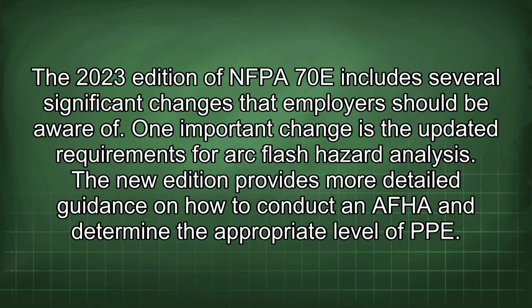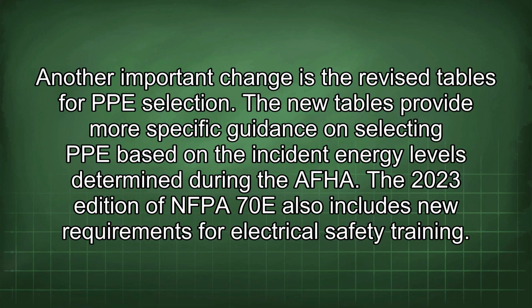One important change is the updated requirements for arc flash hazard analysis. The new edition provides more detailed guidance on how to conduct an arc flash risk assessment and determine the appropriate level of PPE. Another important change is the revised tables for PPE selection. The new tables provide more specific guidance on selecting PPE based on the incident energy levels determined during the assessment.